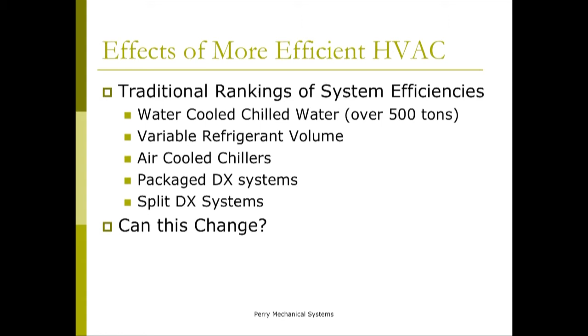This is a busy slide, but if you're looking for more efficient air conditioning equipment, I've shown a chart here with the overall costs for a 300-ton project with 2 chillers—comparing traditional air-cooled chillers, traditional water-cooled chillers, and a premium efficiency water-cooled chiller, which represents some newer technologies out there. There are magnetic chillers now, where the shaft levitates on a magnetic field instead of using oil lubrication, reducing friction losses and increasing efficiency.